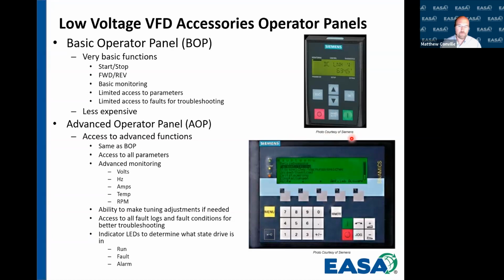troubleshoot a drive fault. With advanced operator panels, now they're not all the same, but for the most part, they're going to give you all the same functionality as the basic operator panel. Also, they're going to give you access to almost all parameters, if not all parameters, and you're going to have advanced monitoring. So the temperature, your speed feedback, all the different things that we've added in, all those different accessories we've added in, you're going to be able to see those on the display. You can even make some tuning adjustments as needed as well. There's one thing we have to be careful about: when we're making tuning adjustments, you might want to see what we call a trace function just to make sure that the drive and the motor are performing the way you want. But you can make changes, slight changes, from the advanced operator panel.